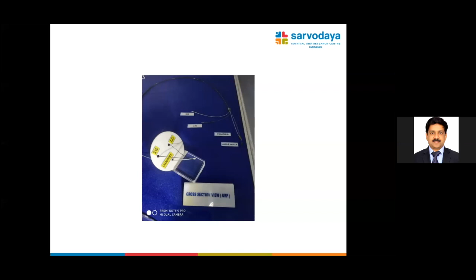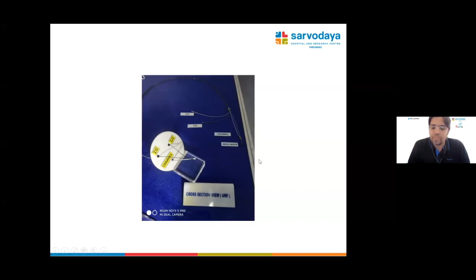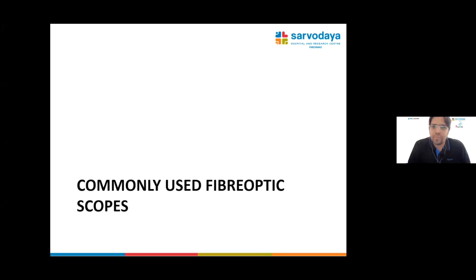So this is a dissected fiber optic ureteroscope, and we can see that this plastic tubing is the instrument channel. This is the light bundle, and this is the image guide, which are basically made up of fiber optic bundles. So coming to commonly used fiber optic scopes, I will be discussing only the most commonly used ones. We know that the most commonly used fiber optic scopes are P7 from Olympus and FlexX 2S from Karl Storz.